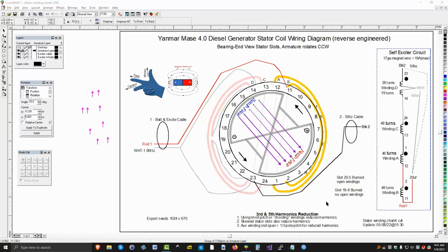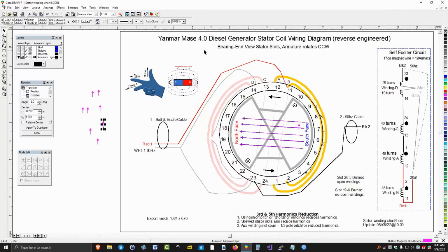I also want you to remember the purpose of these exciter windings. They produce current which through the flux saturates the flux in the rotor. And that's their whole purpose, saturate the rotor flux. And it can alternate like it does here because the rotor has 2 diodes on it. And the diodes in the rotor always keep the current flow in the rotor winding in the same direction, therefore the flux in the rotor is always the same direction. So it's pretty ingenious how this works. So that concludes this video.